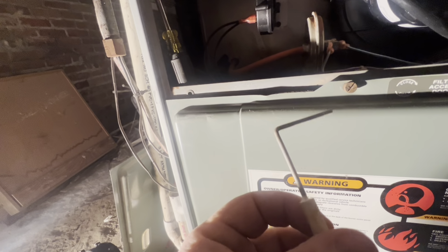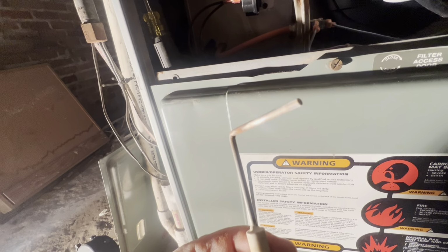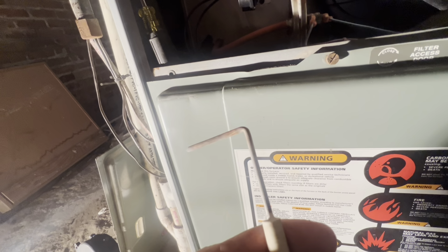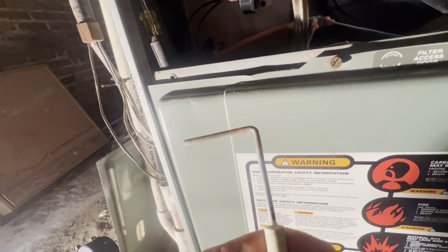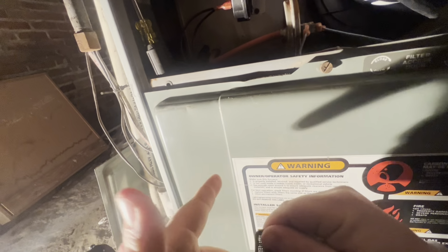Okay guys, so what you got going on here is get yourself a flame rod. Now take a look at that. Look how dirty that is. So we got rust, we got all kinds of buildup going on. Sorry, I got an alarm going off in the background. But we're going to take an abrasive cloth right here, and we're going to wrap it around it just like this. And we're just going to sit here, spinning our fingers, where I get all that junk off of there.